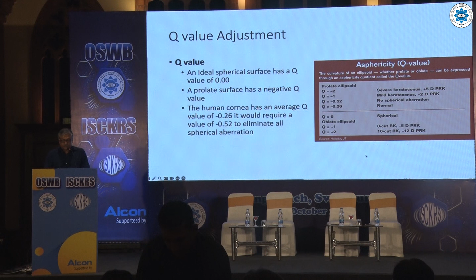Now coming to wavefront optimized treatment. The goal of wavefront optimized LASIK treatment is not only to correct the refractive error, but also to preserve the natural shape of the cornea as much as possible. So in wavefront optimization, we compensate for the peripheral energy losses and give more spots in the peripheral cornea so as to reduce the aberration that's happening. Wavelight has developed an algorithm that adds additional pulses into the periphery to compensate for the spherical aberration that happens in the periphery.